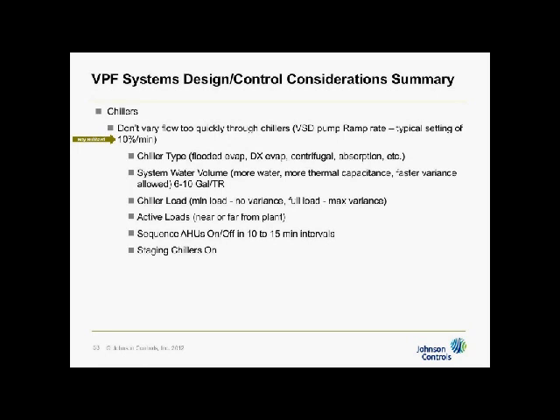Most HVAC systems don't need more than 5. Most of the buildings that have been done by the folks that are going to give you the next webinar usually set them around 5 because they just don't need faster than 5. The building doesn't call for it. Only in special circumstances where you've got some big load that drops off, like a process load or something. But with normal HVAC, 5's plenty, so we usually set them to 10. That doesn't mean they can't go faster. You can set these maybe up to 30. Some systems are 5, some are 10, all the way up to 30. It's not the chiller determining exactly how fast you can go. It's the system determining it for the chiller.